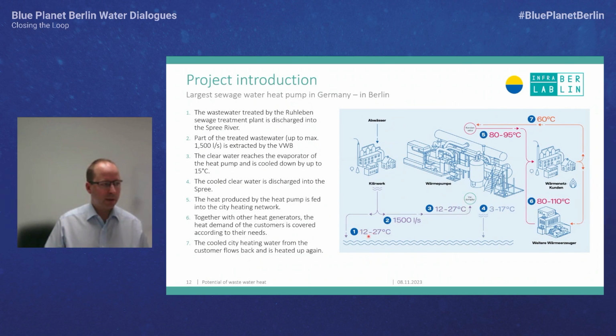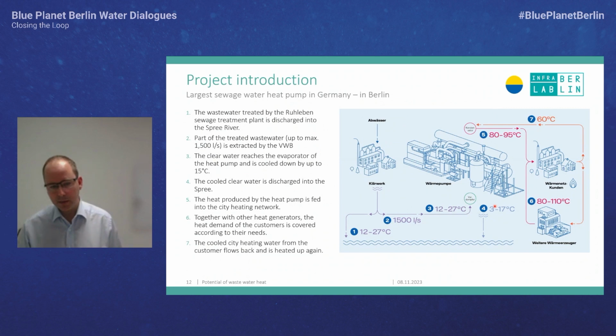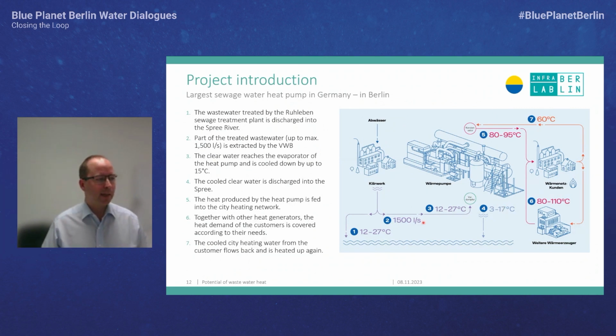So if we get it at 12 degrees C, we cool it down by 9 Kelvin. In summertime from 27 degrees, normal operation would be to cool it down by 10 Kelvin, but the unit is able to cool it down by 15 Kelvin, so we can extract much more heat out of the water.